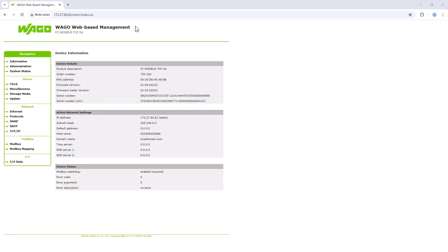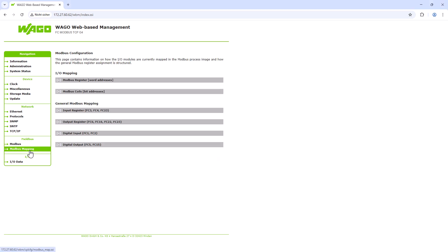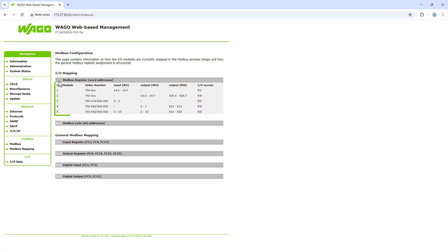WAGO provides a very nice overview in the web-based management of the Modbus coupler for this purpose. So, we switch to the WBM of the Modbus coupler and find the field bus menu Modbus mapping. If we expand the Modbus register item here, all modules are listed in the order they are plugged in.